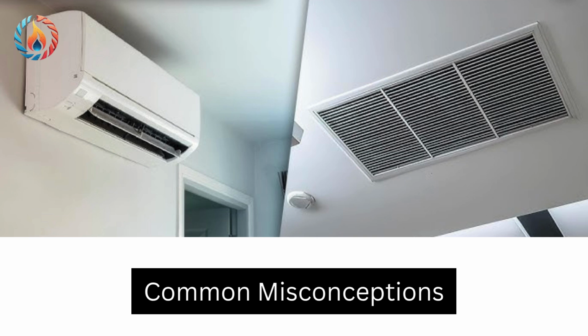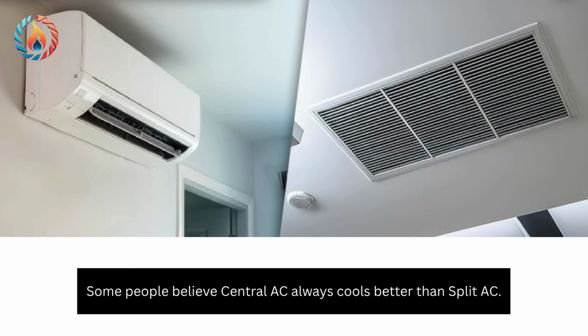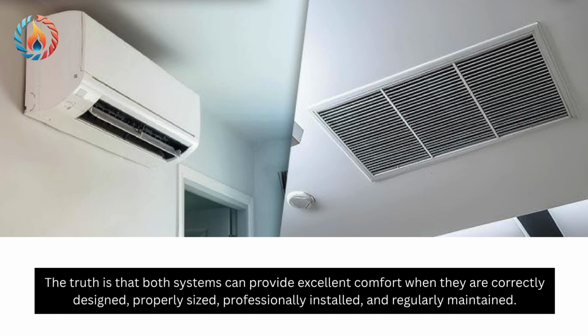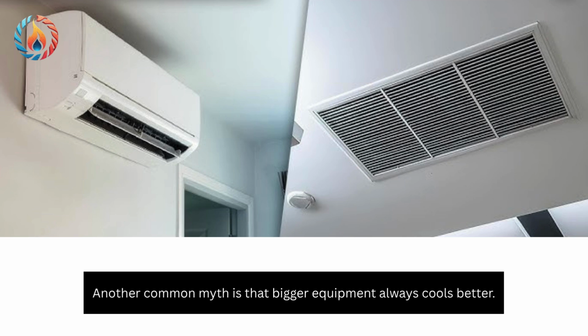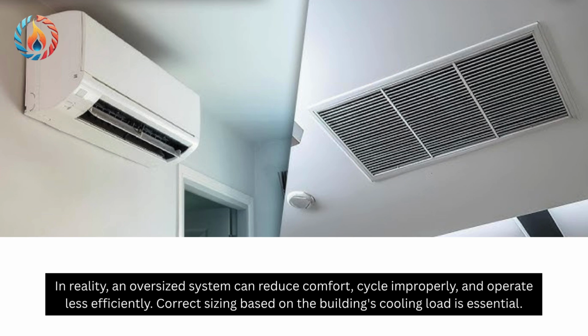Common misconceptions. Some people believe central AC always cools better than split AC. The truth is that both systems can provide excellent comfort when they are correctly designed, properly sized, professionally installed, and regularly maintained. Another common myth is that bigger equipment always cools better. In reality, an oversized system can reduce comfort, cycle improperly, and operate less efficiently. Correct sizing based on the building's cooling load is essential.